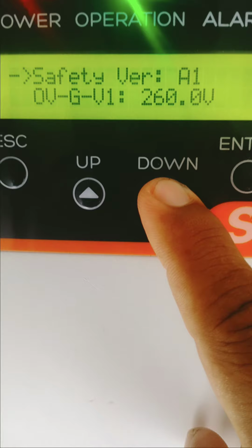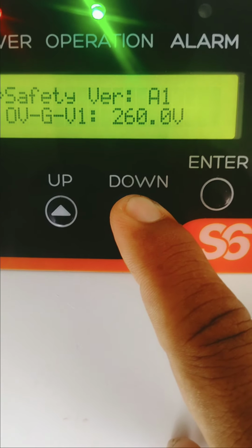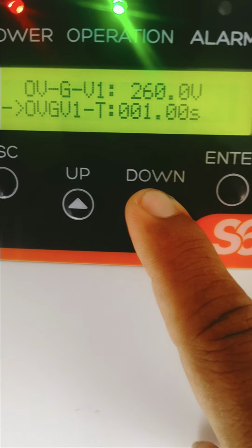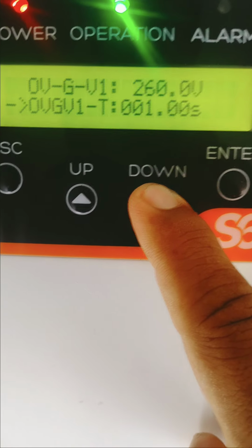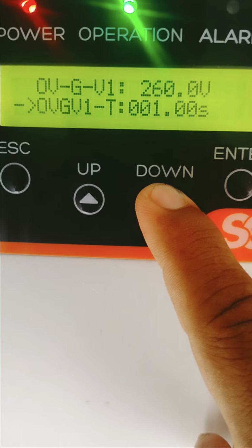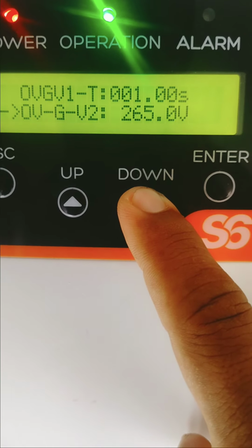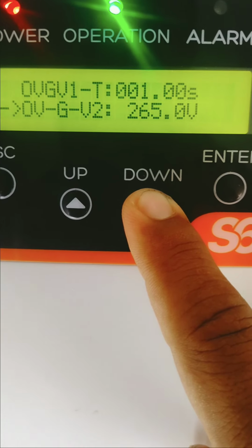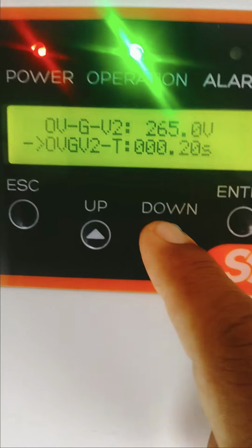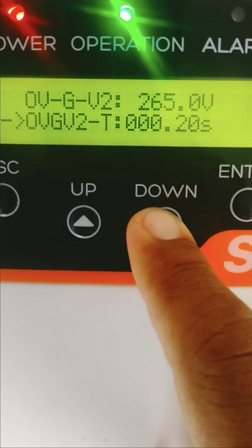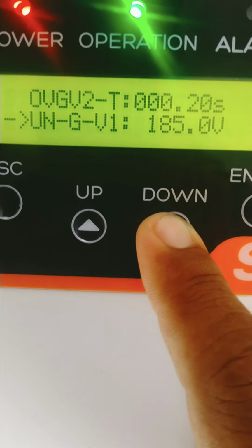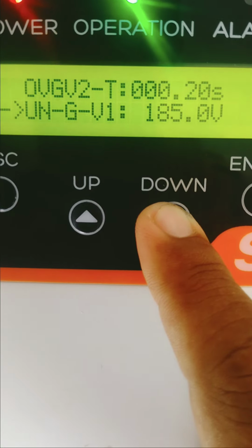In user defined, the over grid frequencies are used. Overgrid frequency 1 is 260. Overgrid frequency 1 is also 260, with a reconnection time of 1 second. Overgrid frequency 2 is 265. So it can go higher. Sorry, that is voltage, my mistake, not frequency.